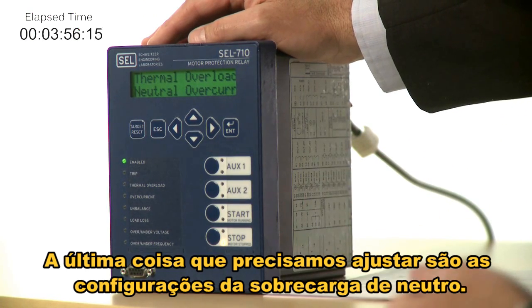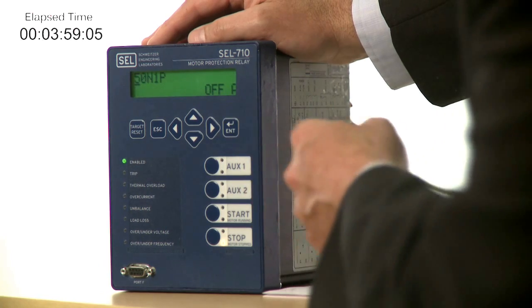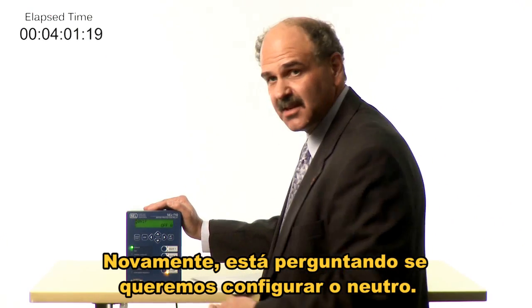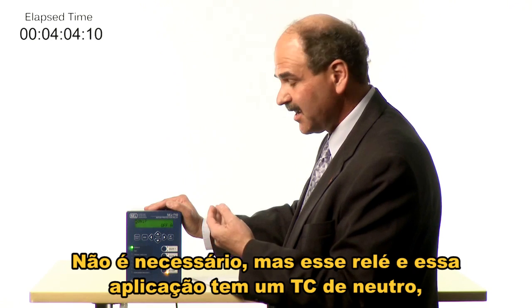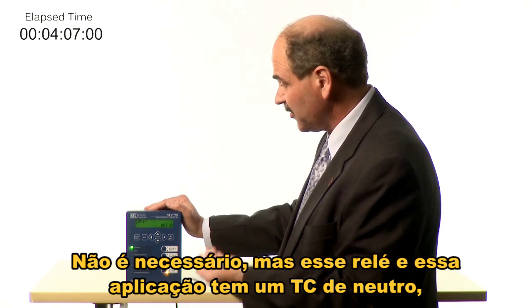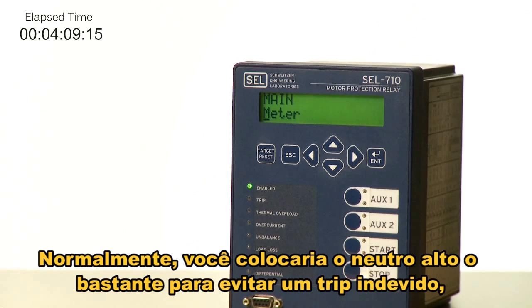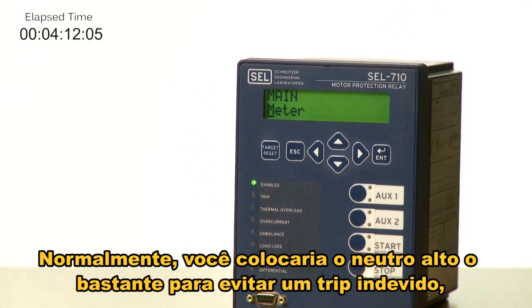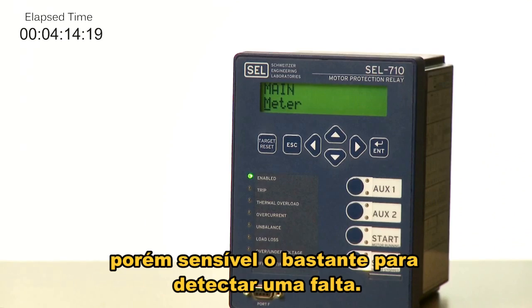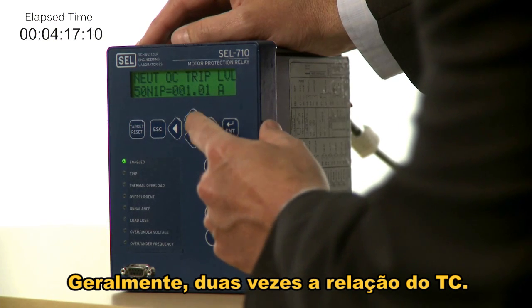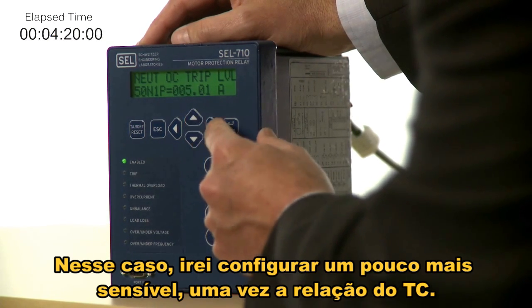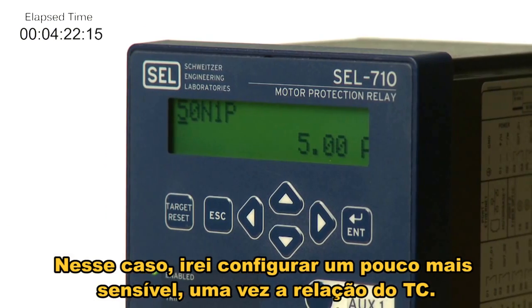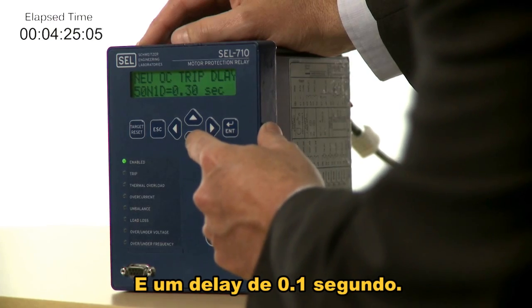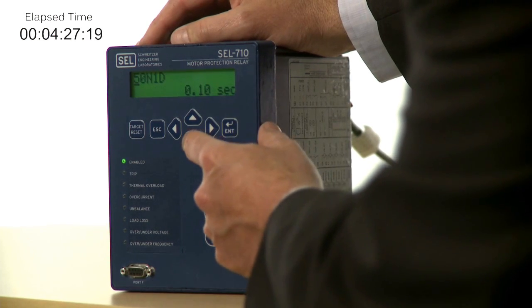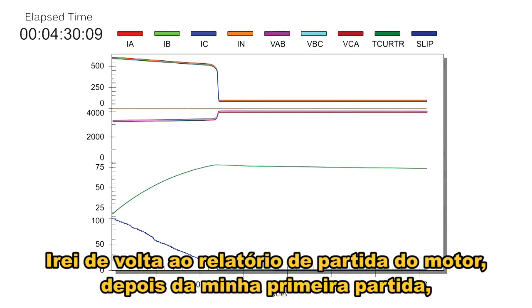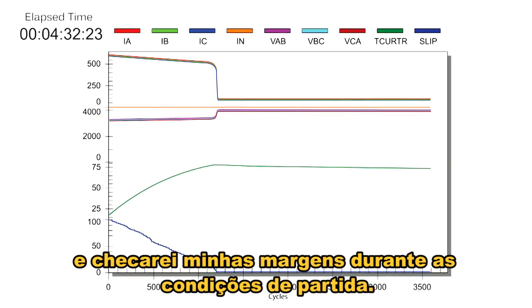The last setting we need to put in is the neutral overload settings. Again, it's asking, do we want to set the neutral overload? It's not required, but this relay and application did have a CT for the neutral, so we're going to go ahead and set those. Typically, you would set the neutral high enough to avoid a nuisance trip, but sensitive enough to detect a fault, typically 2 times the CT rating. In this case, I'm going to set the pickup a little more sensitive at 1 times the CT ratio and a delay of 0.1 seconds. I'll go back to the motor start report after my first start and check my margins during the starting conditions.